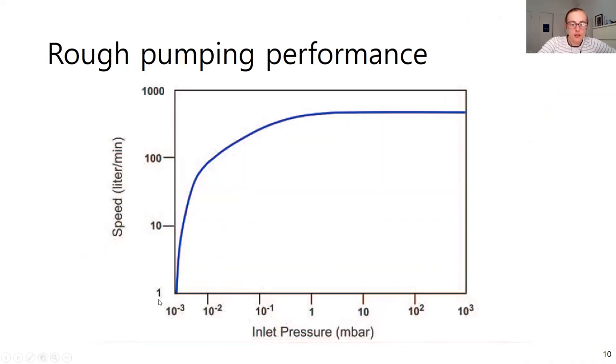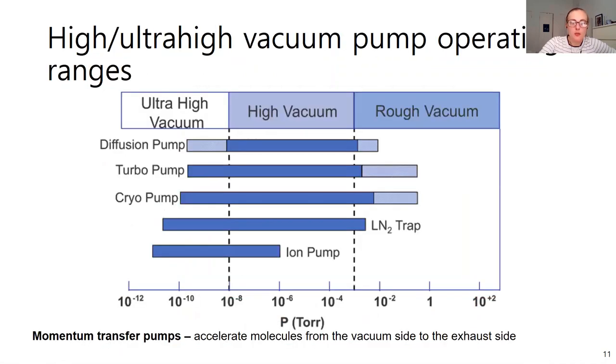This plot here is just showing how fast you're displacing that gas, how you're changing your pressure and the speed that eventually you'll reach some limit that it slows down as your pressure is decreasing. So you'll get to a certain point where the roughing pump reaches its limits at these lower pressures. Then you have to close off the roughing pump chamber and then move on to your high vacuum or ultra high vacuum pumps.